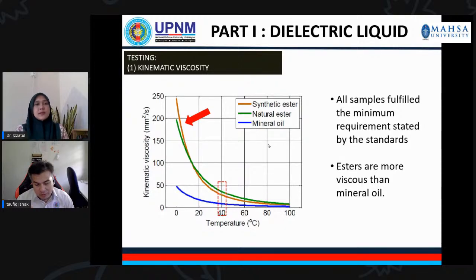For natural ester, including the synthetic ester and also the natural ester, it is recommended that the viscosity for this kind of oil is not more than 50 millimeters squared per second at 40 degrees C. So based on this graph, as you can see here, all the natural ester and also the synthetic ester actually meet the requirement by the standard, which is not more than 50 millimeters squared per second. This is a very good sign that we can use them for transformer.